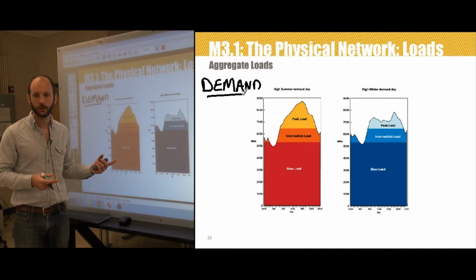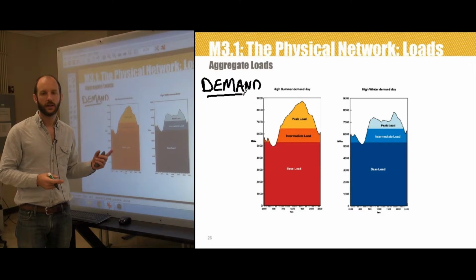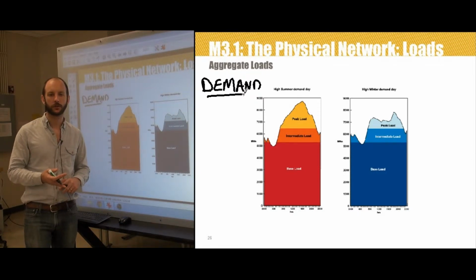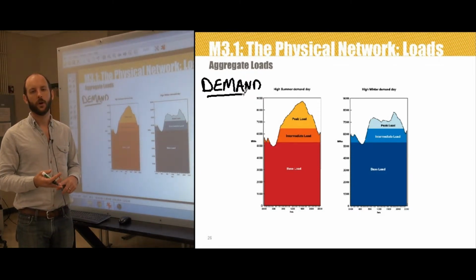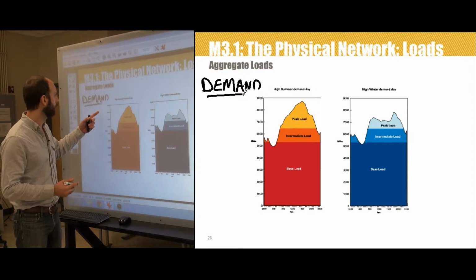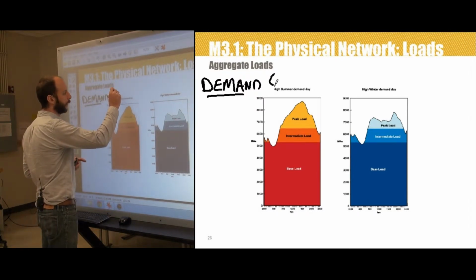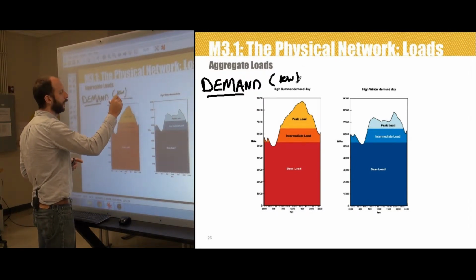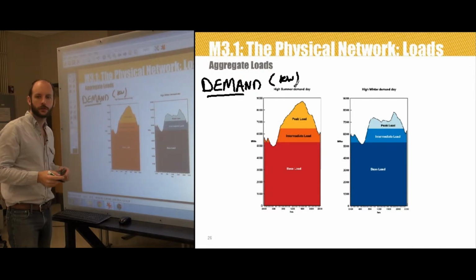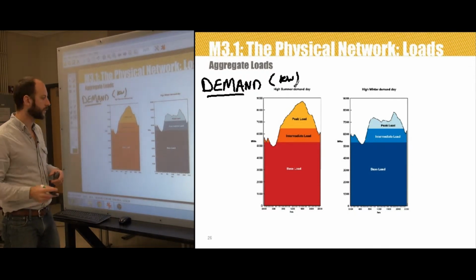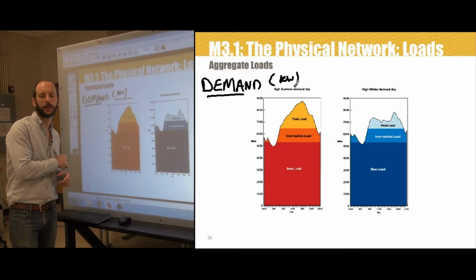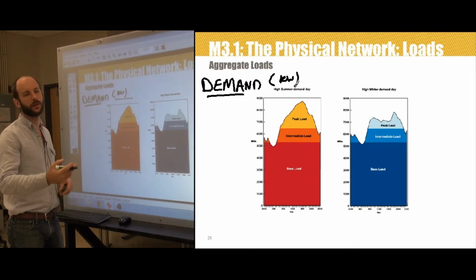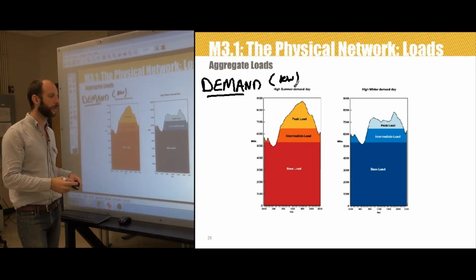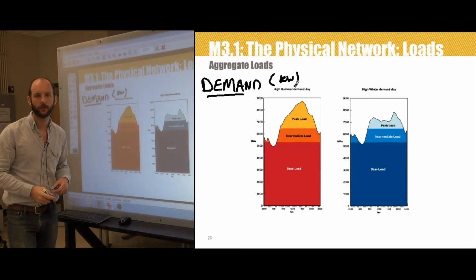The demand really is, what is the aggregate instantaneous need for electric energy from some group of customers? That could mean an individual customer, that could mean a substation; it can have different meanings in different contexts. Energy use, on the other hand, is the total amount of measured electrical energy that is consumed over time. Whereas demand is really a power, in kilowatts, energy use is in kilowatt hours. It's how much energy did I have to supply my customer over the week, or over the day, or over the course of the month, right?